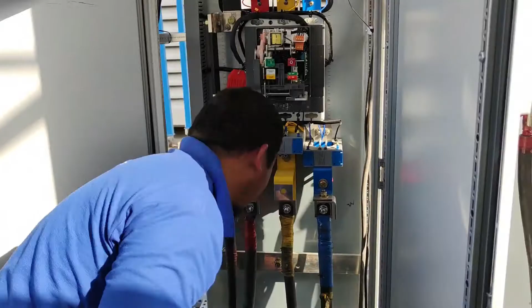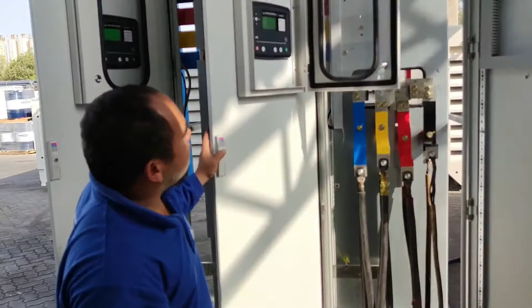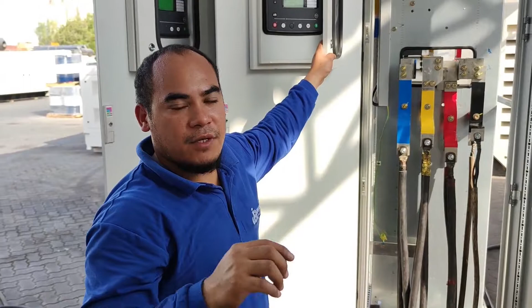Guys, now we already fixed the breaker. The issue is that the trip solenoid was not properly installed, and the auxiliary switches. These give the feedback for your generator close. If they are not fitted properly, they will not give feedback to your generator close relay, so it will trip your breaker and show the alarm of generator failed to close trip also. That is the alarm you will see if it's not properly installed or if there is some failure in it.